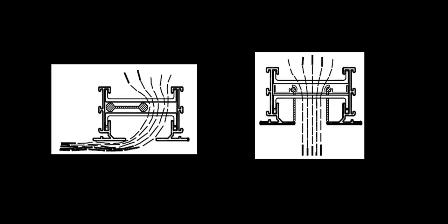For products like Flow Bar, which has either high throw pattern controllers or jet throw pattern controllers, you have performance data that is mixed. The horizontal data shown for a high throw assumes a ceiling effect. The vertical data for the jet throw assumes no ceiling effect.